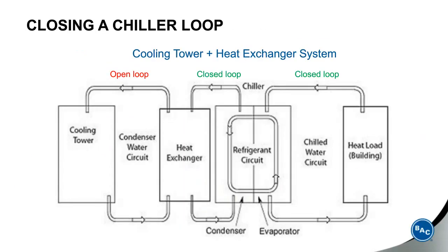Now, closing a chiller loop, we're going to first do it with a cooling tower and heat exchanger. We see the chiller in the middle, and you have the closed loop on the heat load side of the building, the chilled water loop. Then we place a plate and frame heat exchanger and pump the hot fluid from the refrigerant condenser through the closed loop side of the heat exchanger. On the other side of the heat exchanger plates, we're pumping the cooling tower fluid through an open loop to the cooling tower.